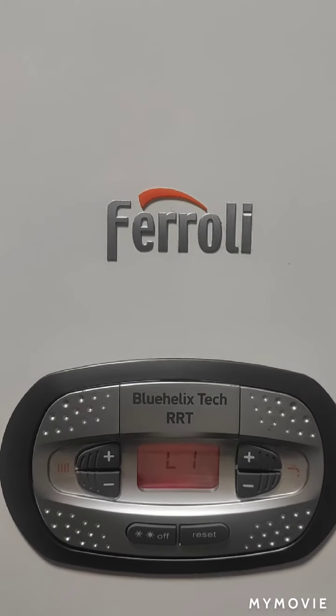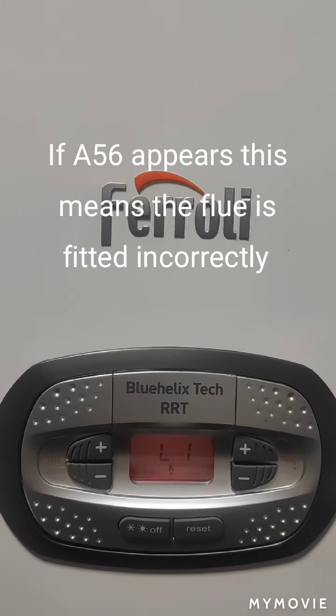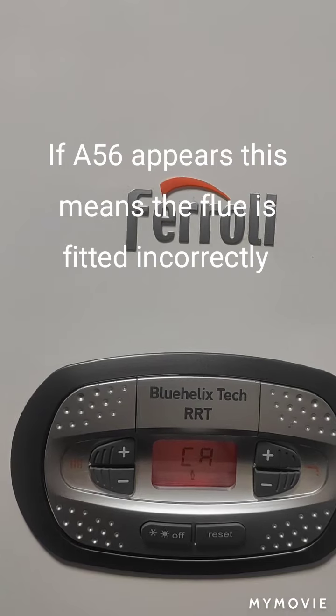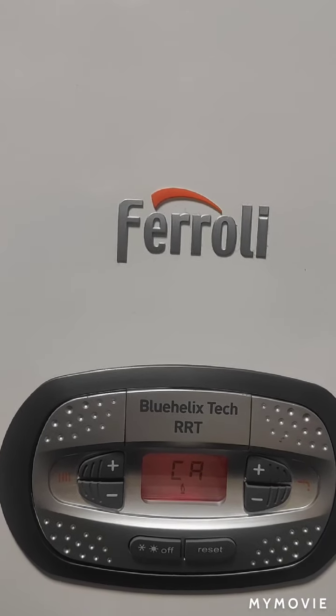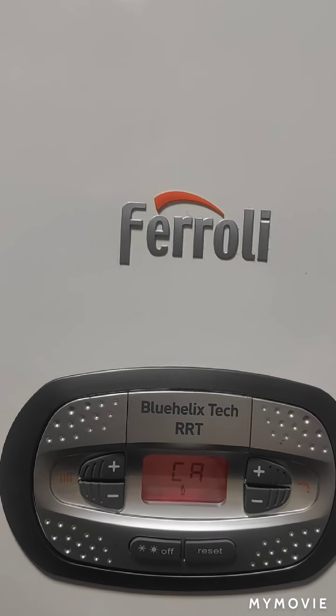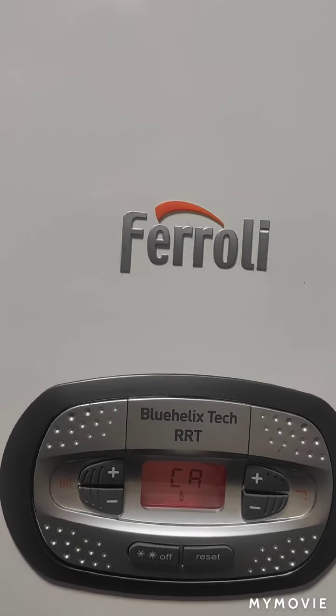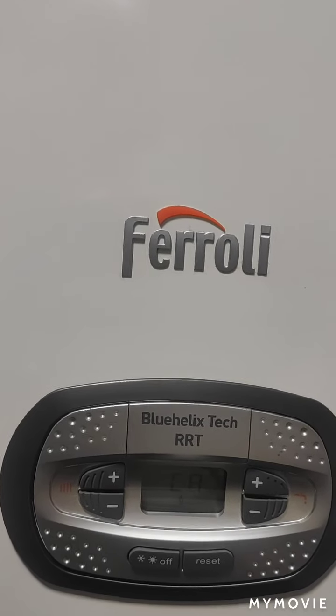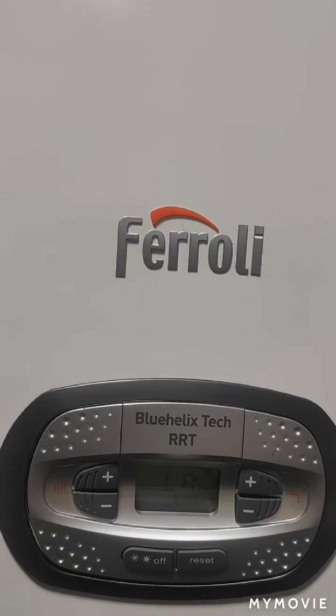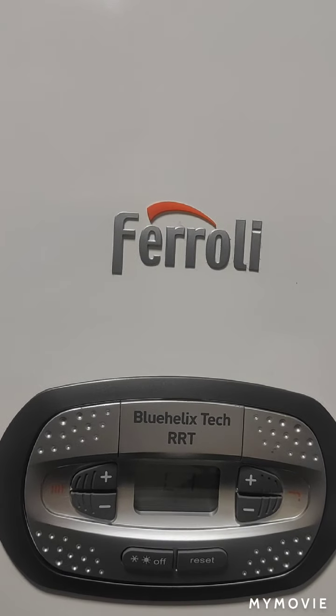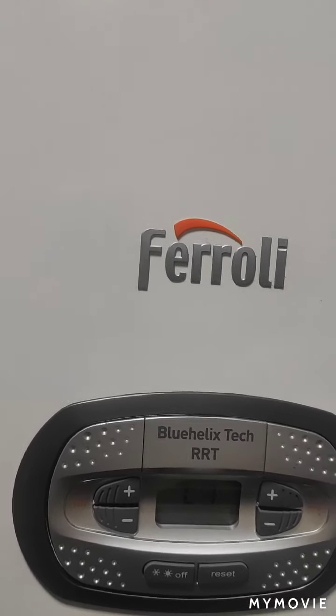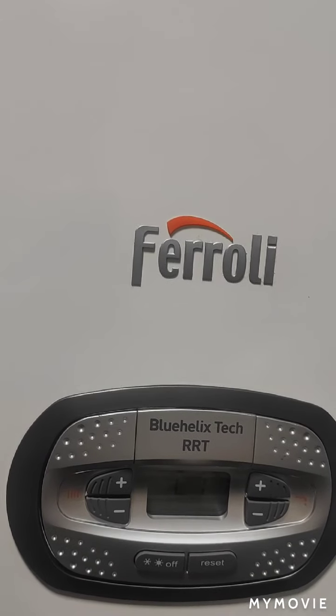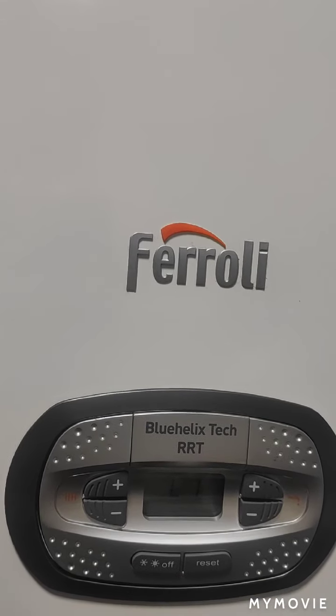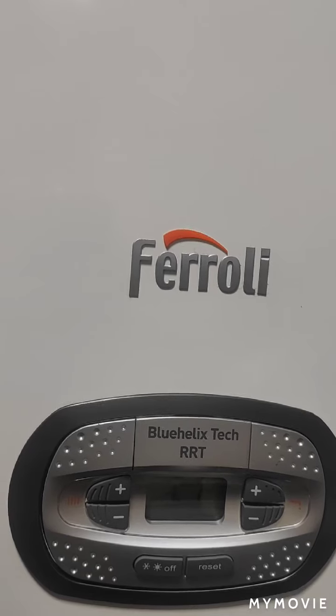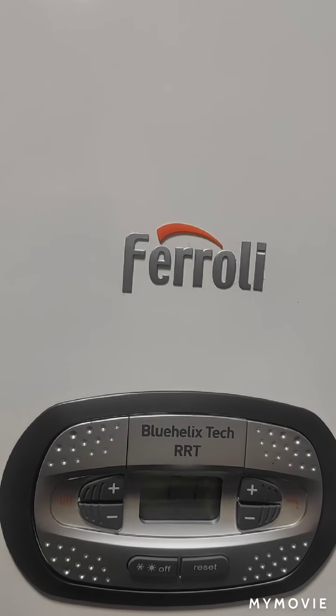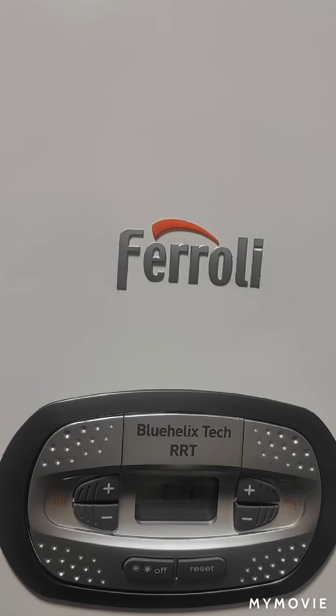This takes probably just over a minute to do, and you must 100% must have the front cover on. I do another test while I'm doing this. I actually test the air intake at the same time, and so you 100% know that the integrity of the flue is working. It's something that we find a lot of people just completely miss, but it's so important, especially on a gas valve that calibrates all the time itself. If it's getting a slight bit of a mixture in, it will never work properly. You'll start getting like a flue fault eventually.